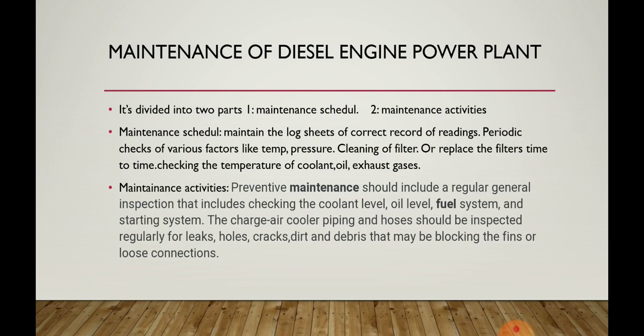The second one is maintenance activities. The preventive maintenance should include regular general inspection, that includes checking of coolant level, oil level, fuel system and the starting system. The charge air cooler piping and hoses should be inspected regularly for leakages, holes, cracks, dirt and debris that may be blocking the fins or loose connections. So careful supervision of the equipment is very important in the maintenance procedure.